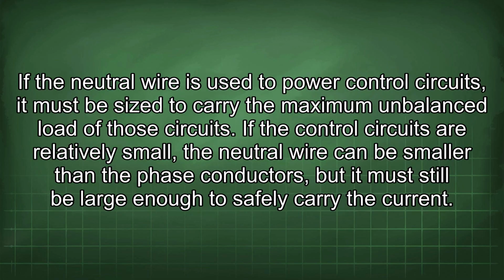If the neutral wire is used to power control circuits, it must be sized to carry the maximum unbalanced load of those circuits. If the control circuits are relatively small, the neutral wire can be smaller than the phase conductors, but it must still be large enough to safely carry the current.